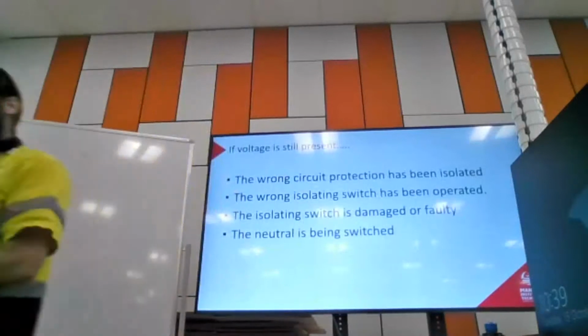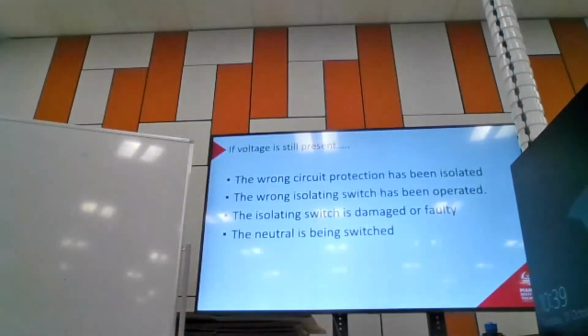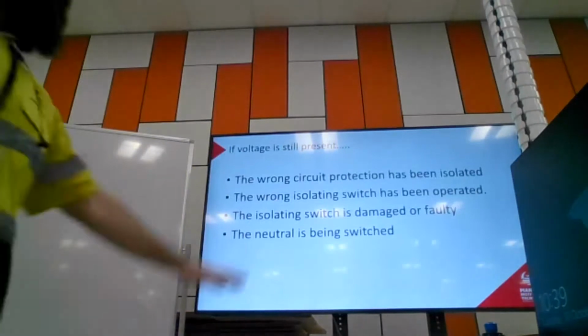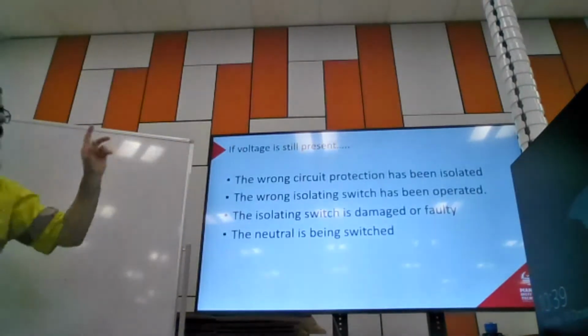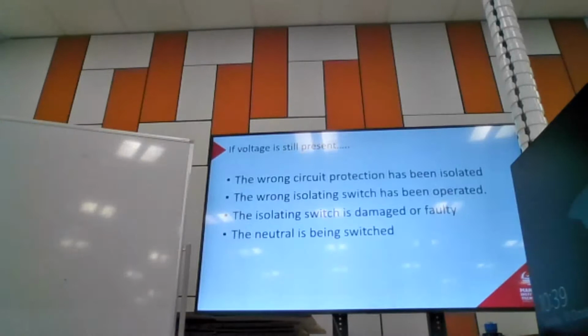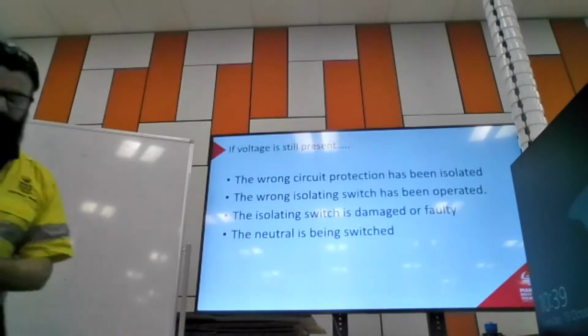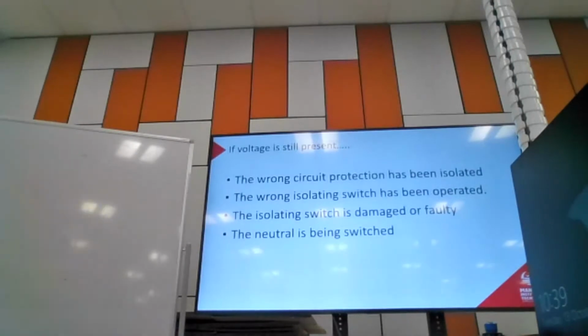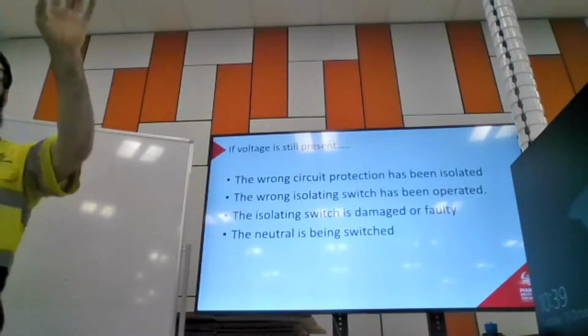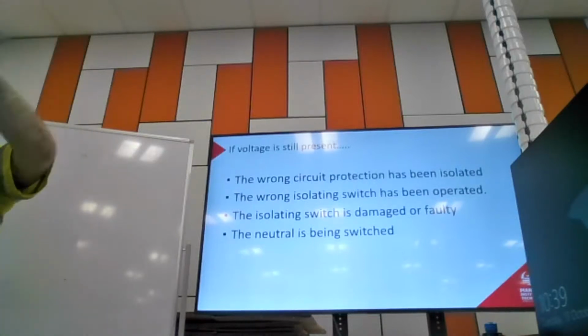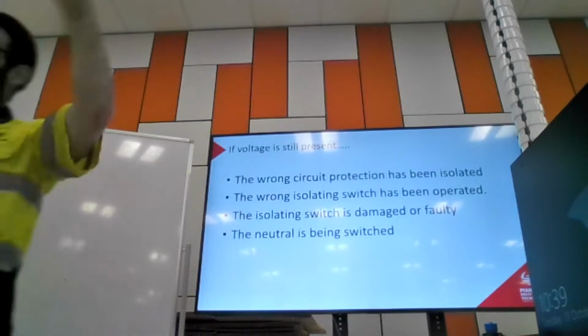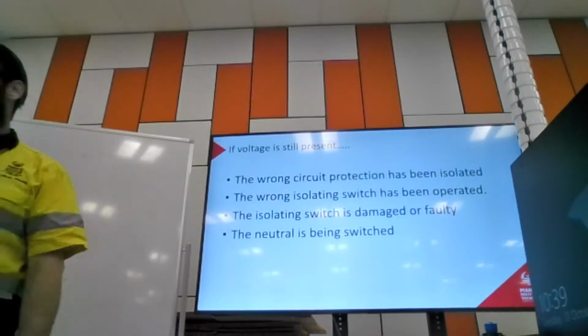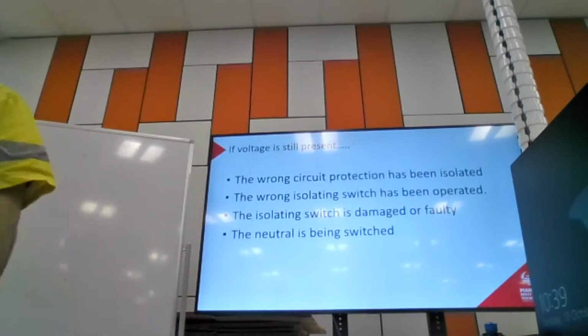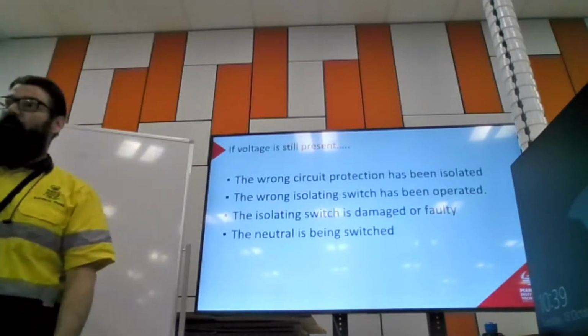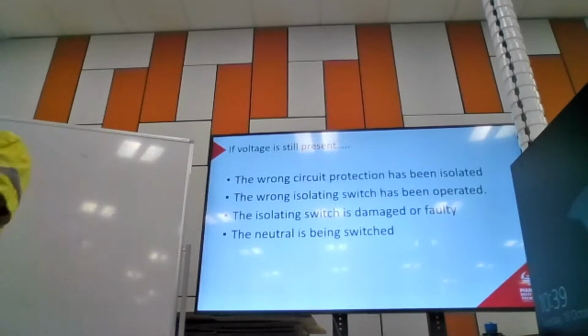So if we go through that whole process to isolate a circuit, we identify it, switch it off, tag it, etc., and we come to do our test, and we find that voltage is still present. What are we going to do? So the first thing we shouldn't do is panic. I've definitely seen that, right? That's what happens when we do that practical task on those boards, and you guys flick the breaker off and you get the wrong one, and then you do the test, and I say it's still live 99% of the time. That's it. That's the end of the test, because most people will not recover from it.